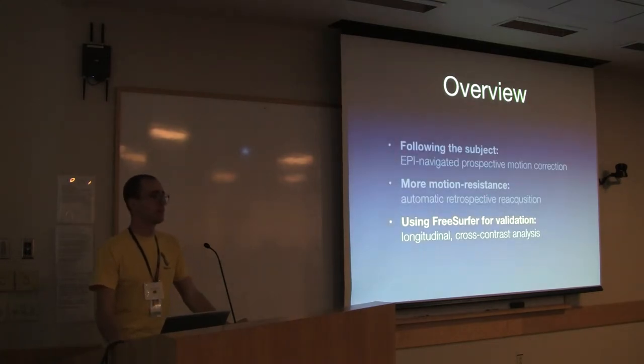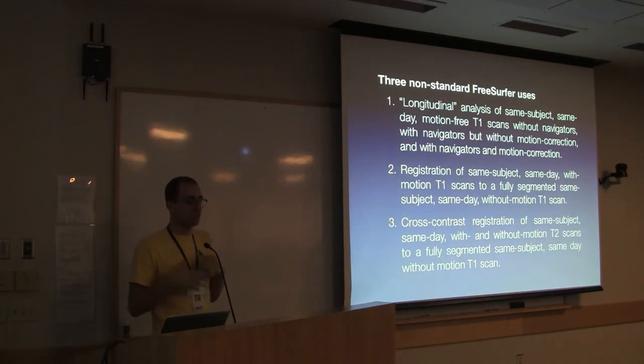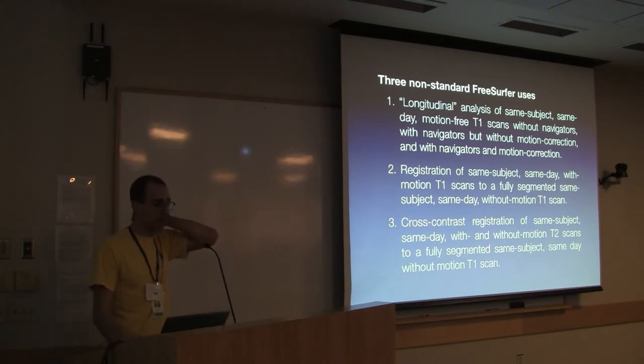That is the system that we've built. Now I want to talk a little bit about how we use FreeSurfer to evaluate it. There were three non-standard FreeSurfer uses here. The first is that we use the longitudinal analysis stream on same subject, same day, motion free scans, without navigators, with navigators, and with navigators but not doing motion correction. The reason we're using longitudinal analysis for this is because we're looking for artificial changes induced in the same subject here. We can order these as if they were time points and then use the unbiased parts of the longitudinal stream to perform a comparison between these time points. If we used a stream that was biased towards any one of those measurements, we might see artifactual changes that aren't really there. Similarly, we then used the cross contrast registration tools a bunch to validate whether our T2 motion correction system was working.